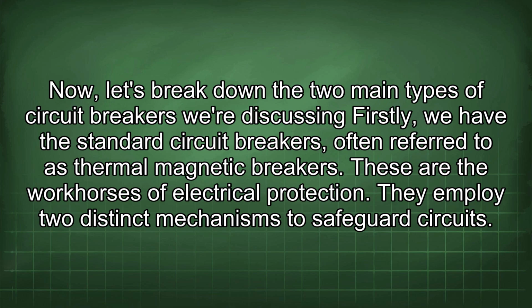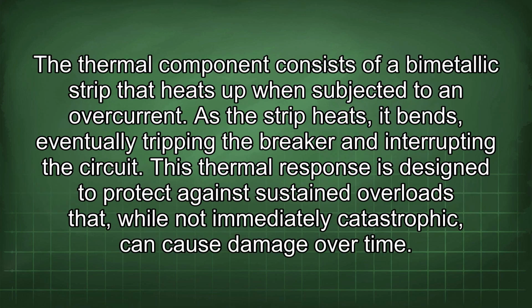They employ two distinct mechanisms to safeguard circuits. The thermal component consists of a bimetallic strip that heats up when subjected to an overcurrent. As the strip heats, it bends, eventually tripping the breaker and interrupting the circuit. This thermal response is designed to protect against sustained overloads that, while not immediately catastrophic, can cause damage over time.